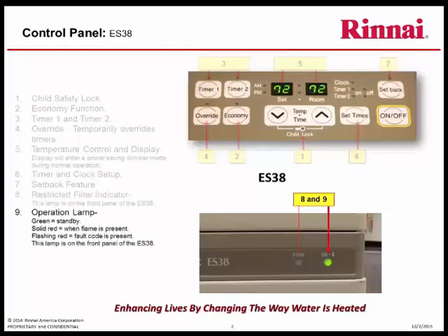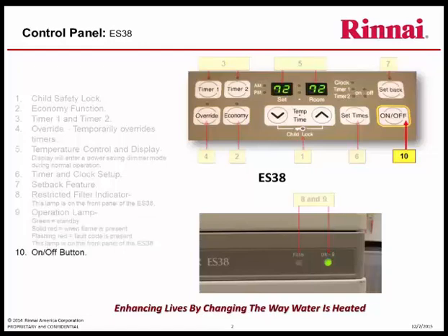Operation lamp. The functioning of this lamp is important as it gives you the current status of the heater. Green is standby, meaning the unit is powered on but not operating. Solid red means flame is present and the furnace is producing warm air. Flashing red indicates a fault code is present. This lamp is also located on the front panel. And finally, the on-off button.